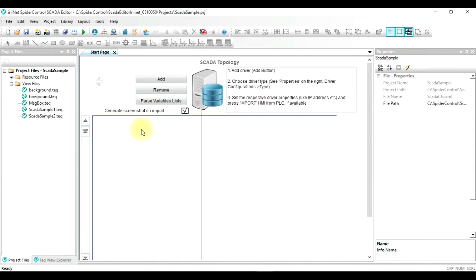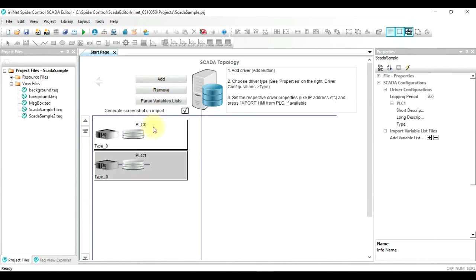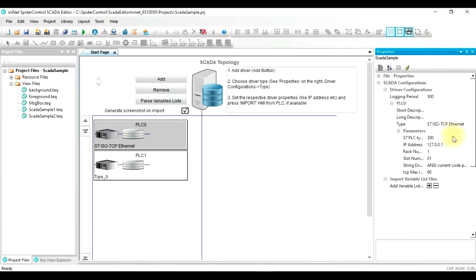We next go to SCADA configuration and add two drivers. The first driver will be our S7 1200, using the protocol S7 ISO TCP. The type is compatible with the 300, and you need to enter the address. The rack number will be 0, slot number will be 1.